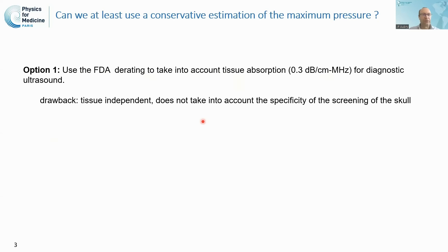The first option is to use the FDA derating, which takes into account the tissue absorption for diagnostic ultrasound. The drawback is that it is tissue-independent — it is very conservative but does not take into account the specificity of the screening of the skull. So we might consider it conservative, but too conservative.